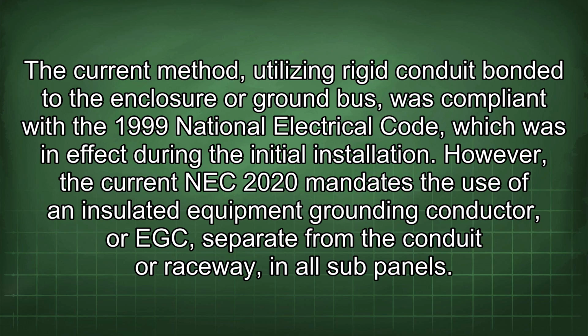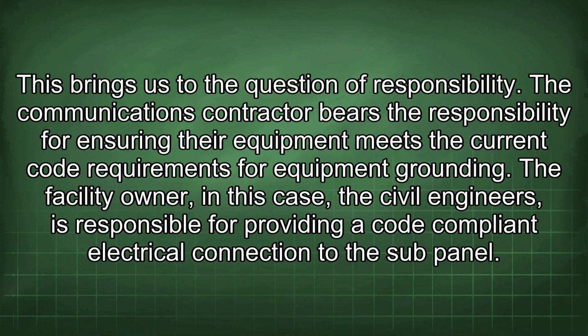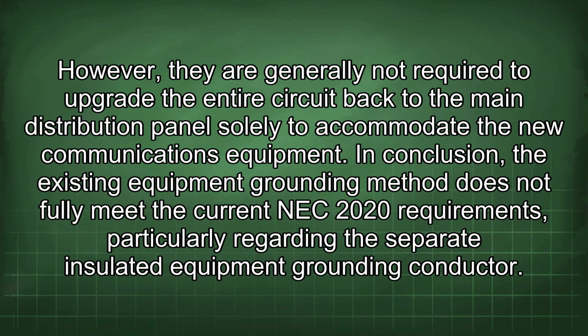However, the current NEC 2020 mandates the use of an insulated equipment grounding conductor, or EGC, separate from the conduit or raceway in all sub-panels. This brings us to the question of responsibility. The communications contractor bears the responsibility for ensuring their equipment meets the current code requirements for equipment grounding. The facility owner, in this case the civil engineers, is responsible for providing a code-compliant electrical connection to the sub-panel. However, they are generally not required to upgrade the entire circuit back to the main distribution panel solely to accommodate the new communications equipment.